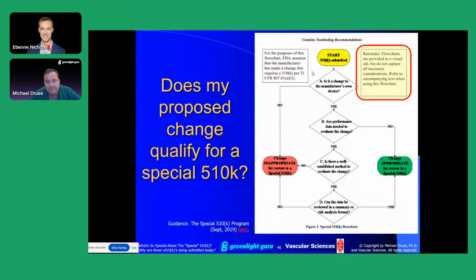This is the flow chart out of the guidance that I referred to earlier, and it steps you through the process at a very high level. Is the change to the manufacturer's own device? Are performance data needed to evaluate the change? Is there a well-established method to evaluate the change? And finally, can the data be reviewed in a summary or risk analysis format? Depending on your answer to each of those decisions, yes or no, it will tell you either yes, the special 510K may be appropriate, or no, it's not.